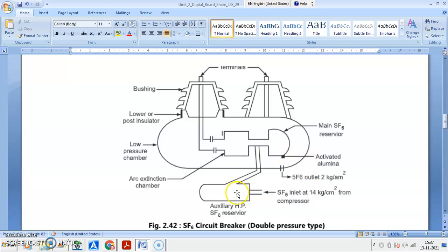You are having high pressure gas which comes over here. Then this high pressure gas is applied inside the arc extinction chamber. When arc extinction is there, the pressure of gas is released. Now low pressure gas is again out. Pressure gets released from 14 to 2. Then again it goes to the compressor. It gets compressed, and again high pressure compressed gas is stored in the tank.